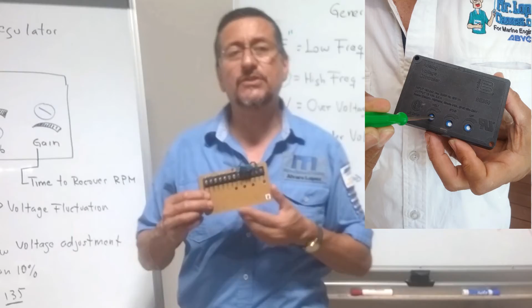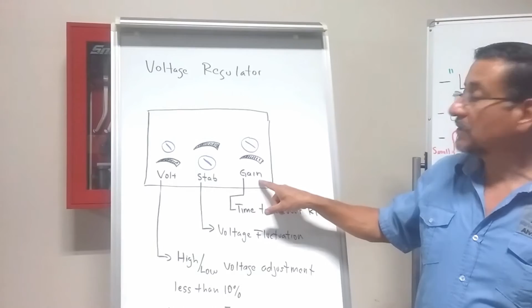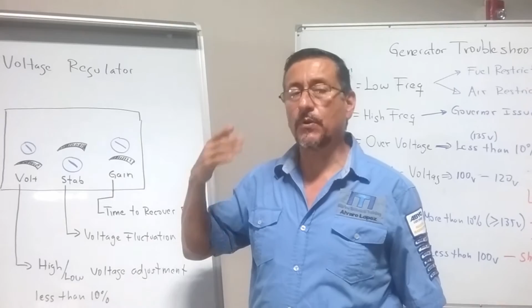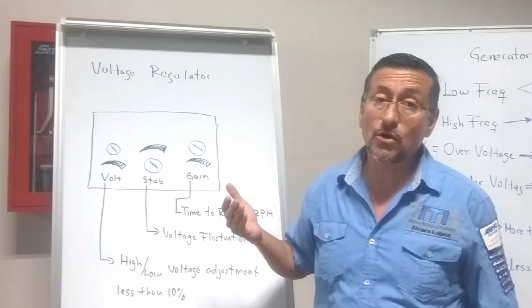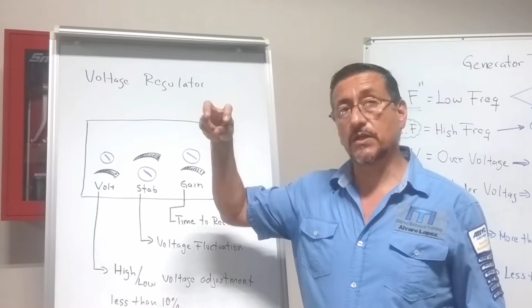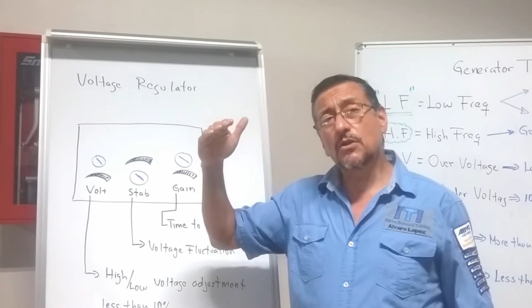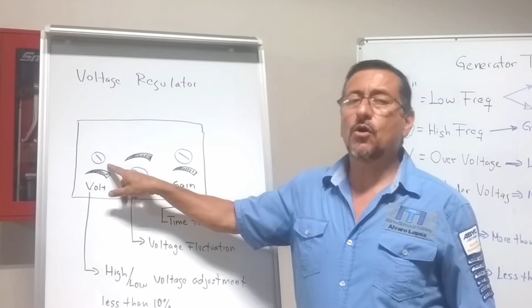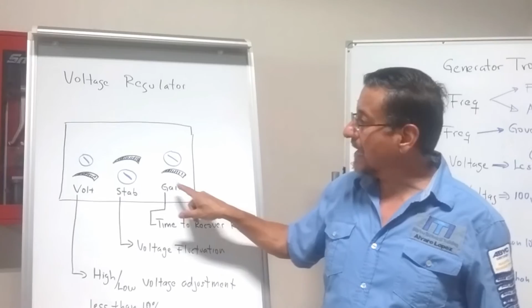This is a typical voltage regulator. All voltage regulators have three spots that you can calibrate with a small flat screwdriver. One spot is for voltage, another spot is for stabilization, and another spot is for gain. If you have a higher output voltage, for example 130 volts, you can calibrate with this spot. You can reduce the voltage, of course, with the engine running and the voltmeter connected at the output breaker of the generator. Or if the output voltage is a little lower, no more than 10%, you can calibrate with this spot, high or low voltage. Right now I am going to explain the other two spots, stabilization and gain.